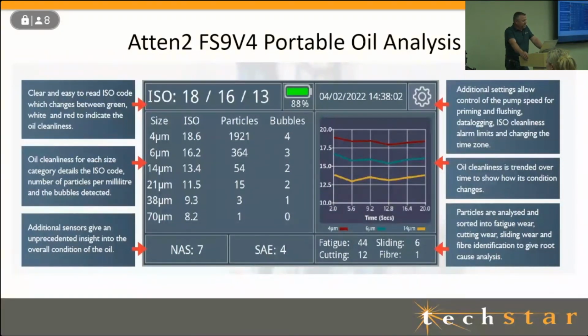If it's more of a cutting wear, say you have gears that are cutting, it can identify those types of particles. Sliding wear as well as fiber. Let's say you have a filter that's breaking down and releasing fibers into your system. You're able to measure those values as well. Like I mentioned, for all of this information that you see here, there are Modbus registers for each one of these values. So if you decided you wanted to go with an online sensor, you could basically map these values into whichever system you want to bring them into.